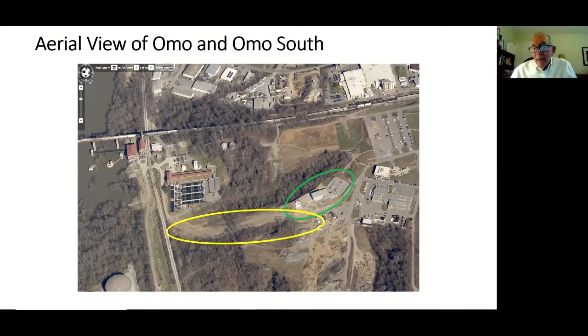We also installed a totally new electric substation with step-down transformers here on this site, and you can tell it's a high-powered substation. It actually has the capacity to bring in 69 kV, power not just for the Omohundro water plant, but a number of other treatment facilities in the area, and we can power that entire campus from this substation. TVA is under agreement to deliver power to this substation, and beyond this point, we control and manage what happens from here. It's totally redundant, one half does what the other half does.